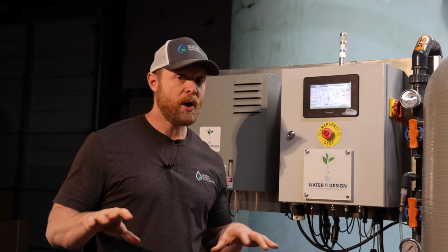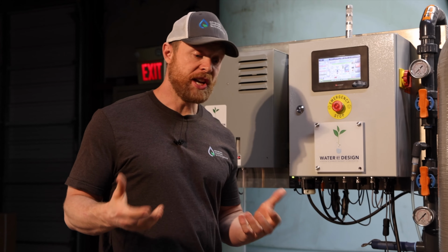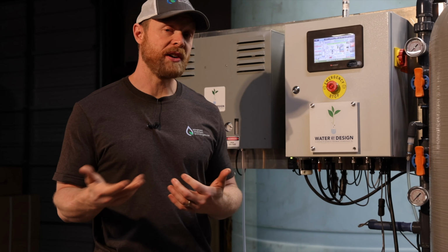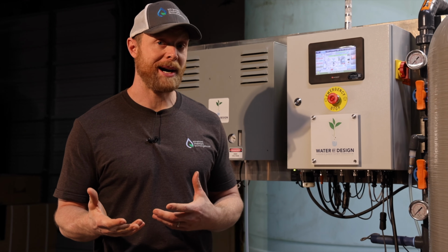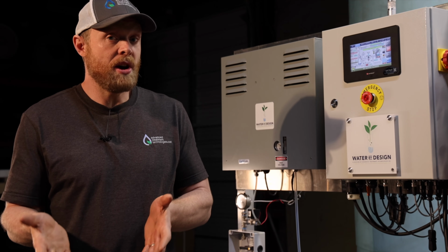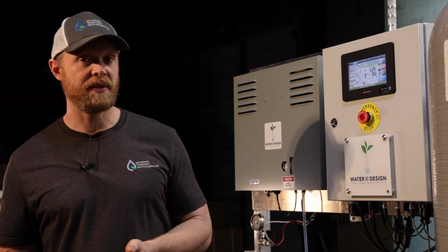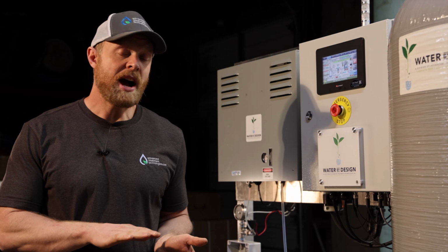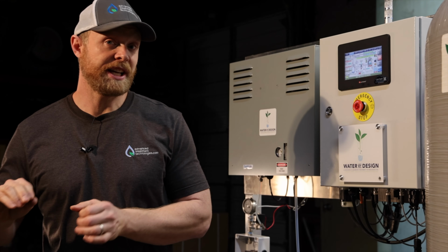Now, there's a couple qualifying things that you need to consider. This would be with the assumption that your line is relatively clean or completely clean of biofilm. So if you've just flushed or if it's a new pipe installation, whatever, 600 may be enough, but if you already know that you have some growth in there, especially if it's significant, 600 may not be enough for you to clean those lines out.